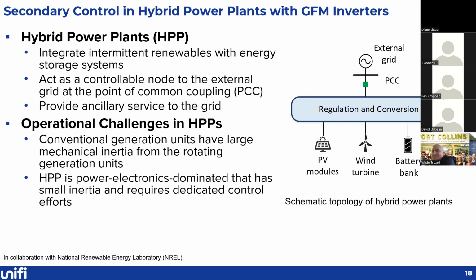Particularly for hybrid power plants, this is not only in the distribution system, but also in the generation or transmission systems. Hybrid power plants can be used to integrate inverter-based resources such as PV panels, wind turbines, or battery banks. The whole hybrid power plant can be seen as a controllable node to the external grid at the point of common coupling. And definitely, the HPP can provide auxiliary services to the external grid.